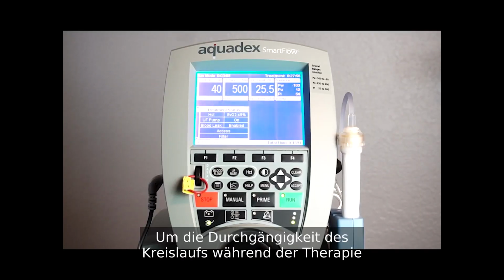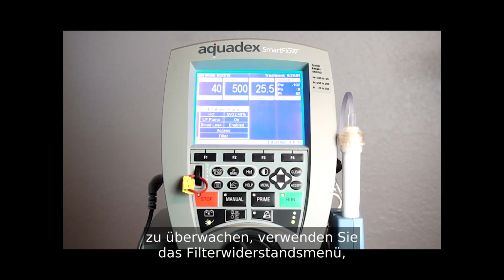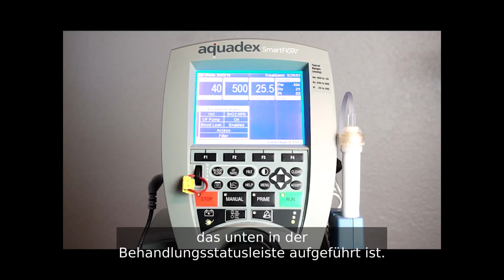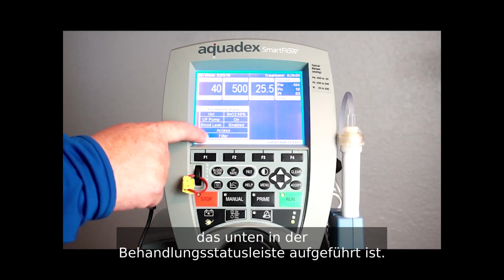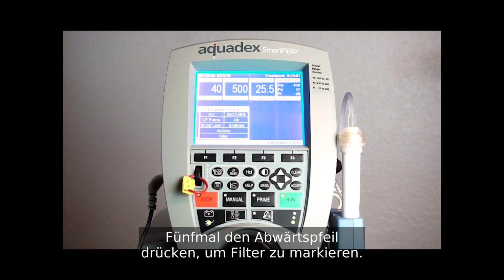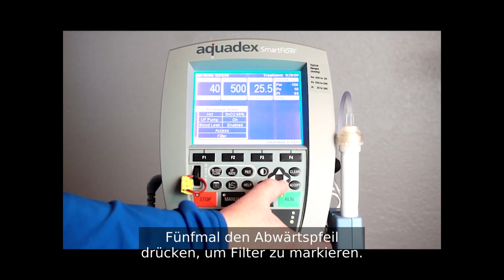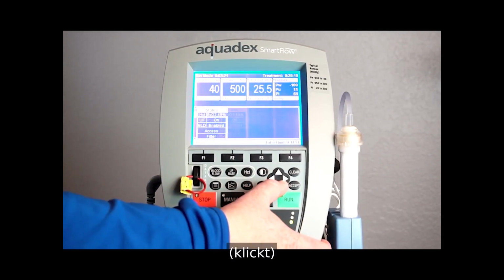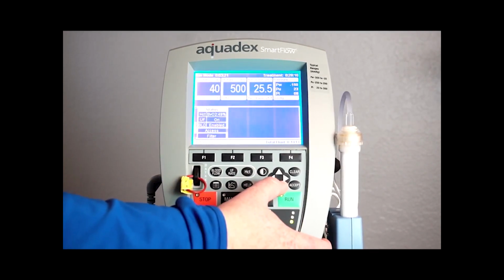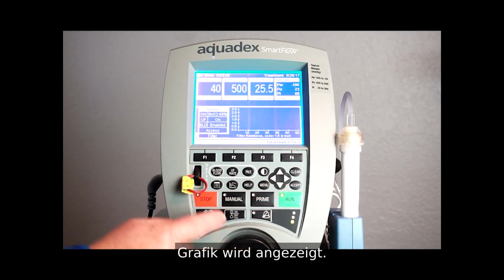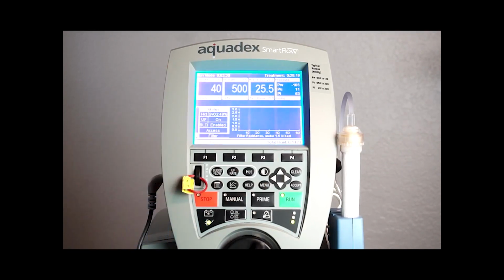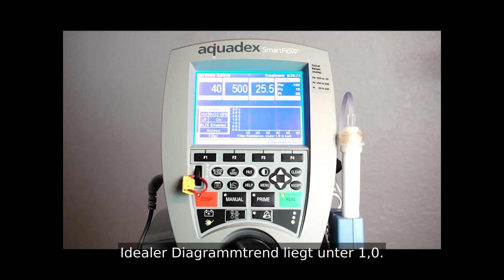SVO2 always displayed next to hematocrit while hematocrit is enabled. To monitor the patency of the circuit during therapy, utilize the filter resistance menu listed at the bottom of the treatment status bar. Press the down arrow 5 times to highlight filter. Graph will be displayed. Ideal graph trend is below 1.0.